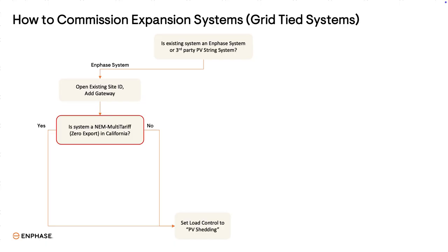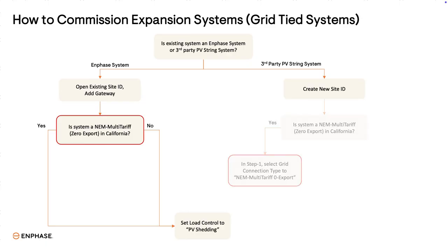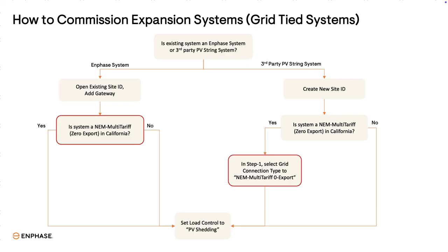Back to the top of the decision tree: if the system is a third-party PV string system, you must create a new Site ID. If the system is NEM multi-tariff zero export in California, set the grid connection type in step 1 to NEM multi-tariff zero export. Then set load control to PV shedding, regardless of whether or not it's a NEM multi-tariff system.